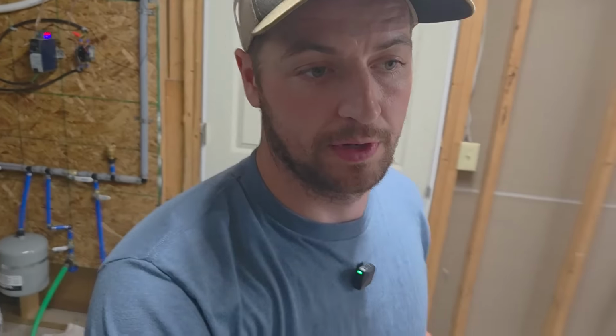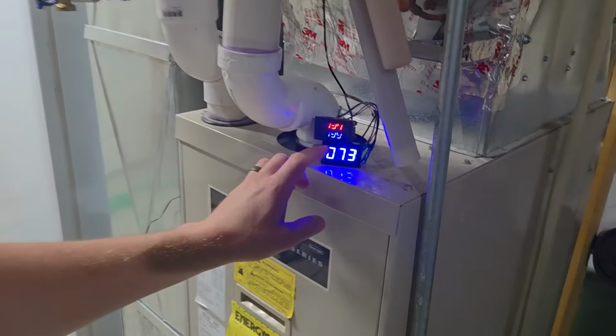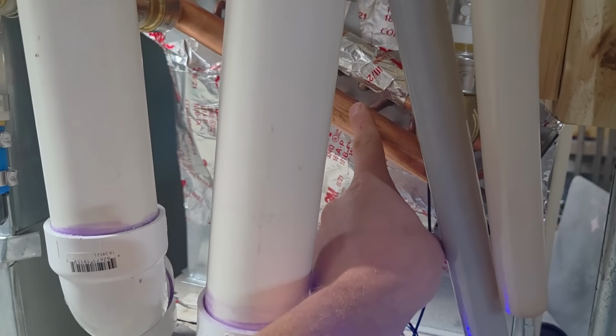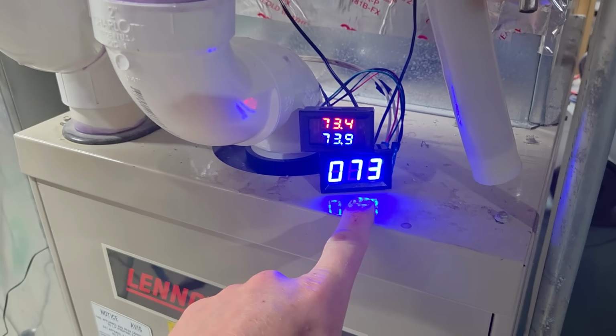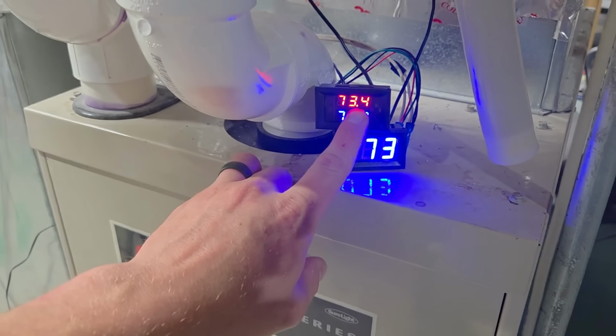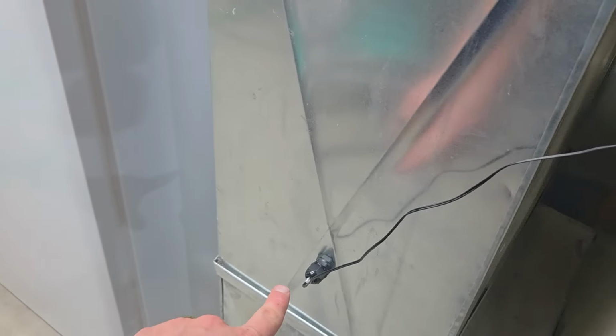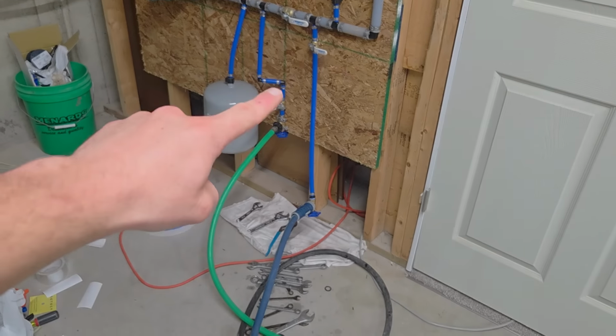And then if we come over to here, I've got a thermocouple on the copper tube here on the heat exchanger. So the temperature of the heat exchanger is 73 degrees. This is the incoming air reading off that thermocouple. And this is the outgoing air reading off that thermocouple up there. And then my drain right here is hooked up to this hose, which runs outside. Let's turn the water on and see what we get for temperature readings.